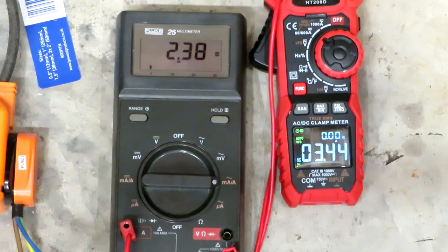So I've just engaged the hold feature in our clamp meters, but you can see that the readings are quite different. The Fluke 25 meter is measuring an awful lot lower, about 1 amp lower. The reason we're getting such a difference between the Fluke meter and the KAIWEETS meter is that the Fluke meter is getting quite confused because there's so much electrical noise on the AC line which is being generated by our VFD, whereas our KAIWEETS meter is indicating 3.4 amps.